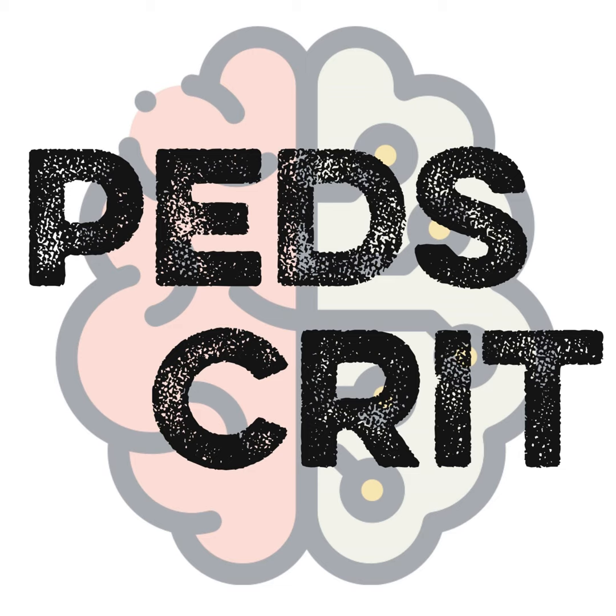And so now, if we go back to that idea of flow trigger, you have air that's leaking out constantly. Think back to the ventilator where that pipe leaves the ventilator. It senses flow. It's constantly going out, and we've set our flow trigger really low so that the ventilator says, oh, they're trying to breathe. Let me give them a breath, give a breath, give a breath, just one after another. And so that's what we talk about with this idea of auto-triggering.